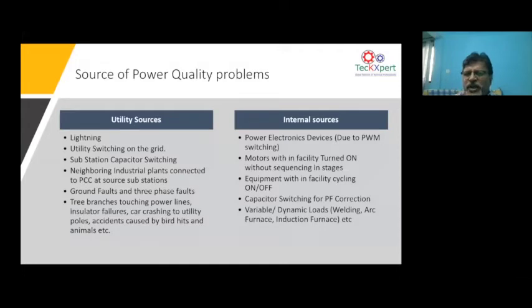When it comes to power quality problems, there are a couple of factors which cause them. Certain things could be the utility sources. When I say utility sources, as I said before, lightning can create an impulse. A substation capacitor bank switching can create an oscillation in the voltage. Those two things are short duration, microsecond or millisecond variations. Similarly, a neighboring industrial plant, a plant next to your building or next to your factory, can also cause a power quality problem. Then there are faults on the utility network.